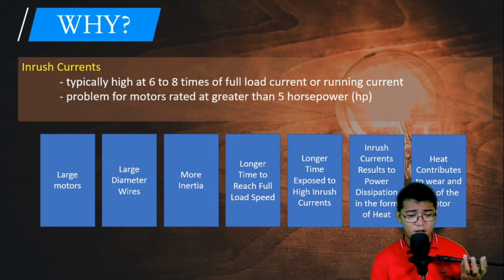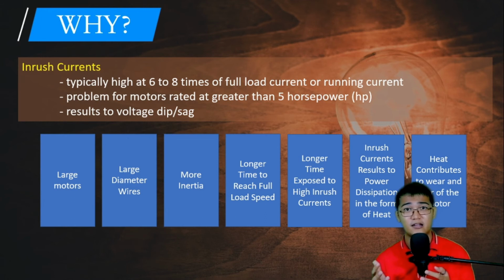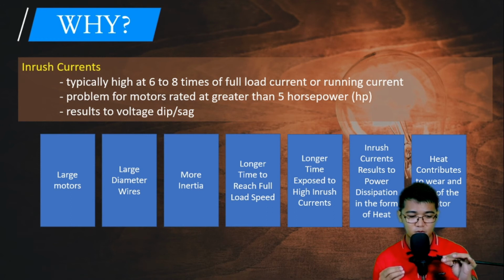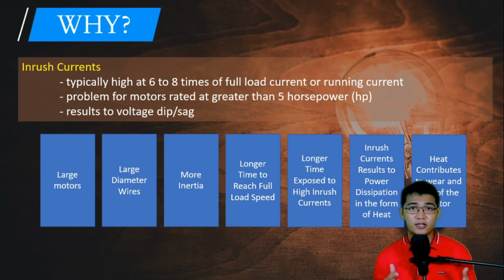Now another result of an inrush current is actually a voltage dip or sag. So again, nabanggit natin na itong mga motors natin is actually connected to our bus bar at yung bus bar natin, yung supply na dumadaan dyan is from the generator. This means that whatever is the voltage applied on that bus bar will actually be the voltage supplied to our electric motors. In other words, our electric motors are connected in parallel since voltages in parallel are actually equal.